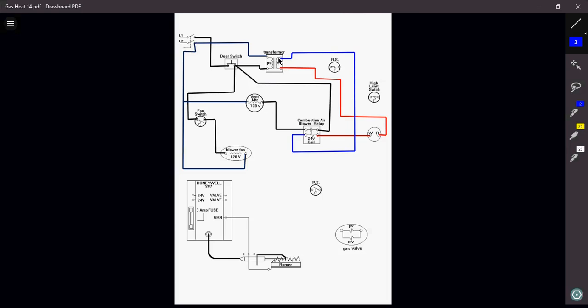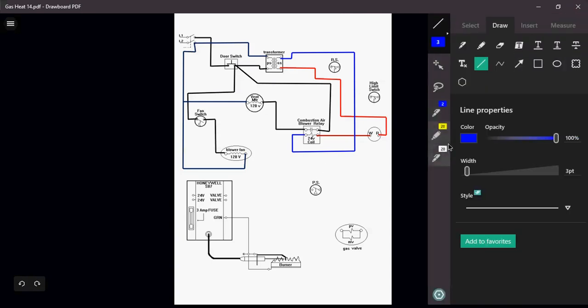So now, like I said, I got to go in 2 separate directions here, right? They're going to be wired in parallel. I still have to do my safeties, 1, 2, 3. So out of my W, and again, you may not necessarily have 2 wires coming right out of the thermostat. That junction point could be anywhere in that furnace. It could be at a circuit board, it could be at a terminal strip, it could be wherever this person wired this furnace. So you're going to have to look and find that wire.